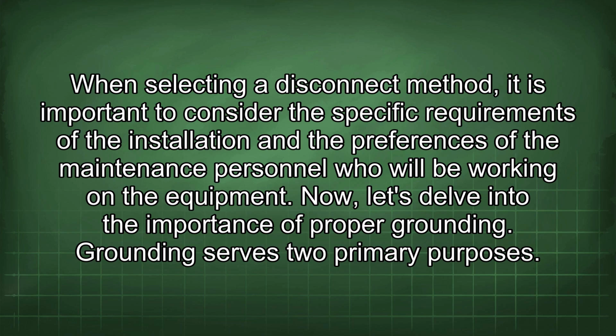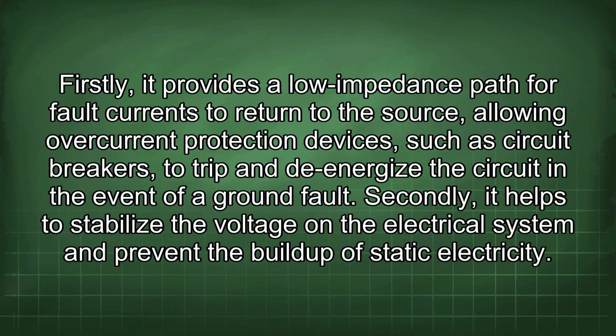Now, let's delve into the importance of proper grounding. Grounding serves two primary purposes. Firstly, it provides a low-impedance path for fault currents to return to the source, allowing overcurrent protection devices, such as circuit breakers, to trip and de-energize the circuit in the event of a ground fault. Secondly, it helps to stabilize the voltage on the electrical system and prevent the buildup of static electricity.